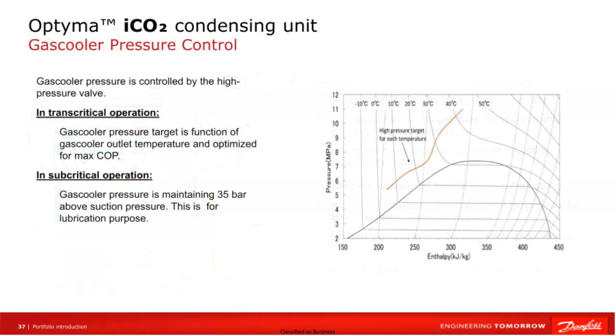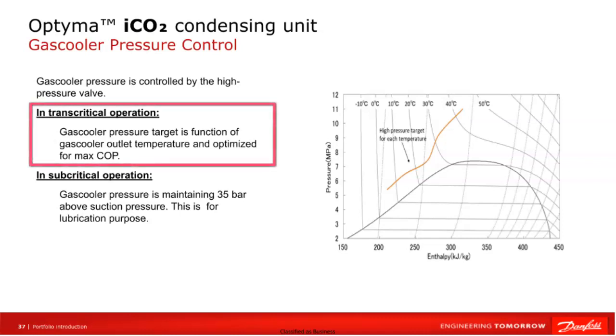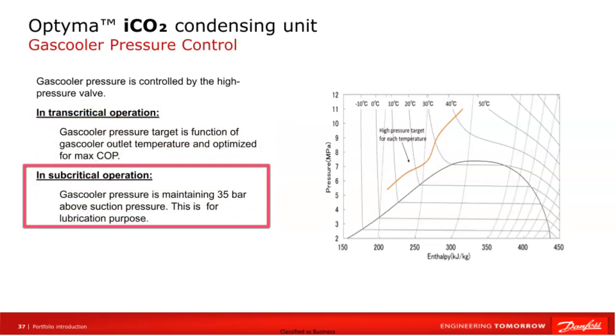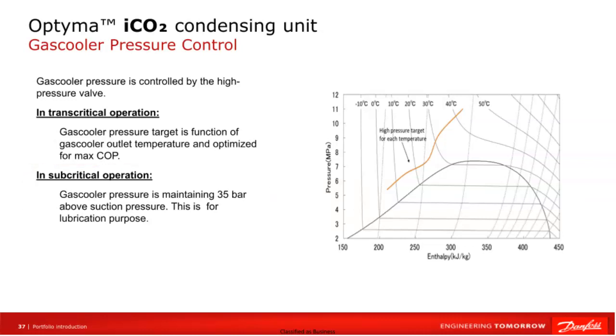So on this slide, I see it's a repetition of the gas cooler control loop. The high pressure valve controls gas cooler pressure depending on the temperature at its outlet. In transcritical operation, above 25 degrees Celsius outside, the high pressure regulation valve optimizes COP. In subcritical operation, below 25 degrees Celsius, the valve maintains a pressure of 35 bar above the suction pressure. This relates to the operation envelope of the compressor.